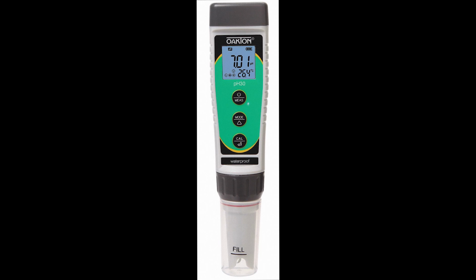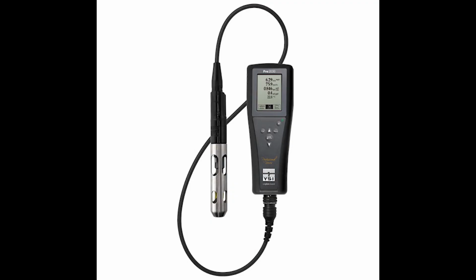Pour out any remaining KCl from the cap, rinse the cap, then add fresh KCl to the cap line. Rinse off the DO meter probe and flush the conductivity ports with tap water. You may use the conductivity port brush at this time to clear the ports by inserting the brush and moving it in and out 8 to 10 times per port.